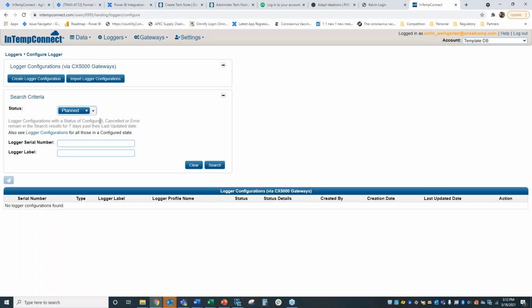How do we turn off the alarm after it's triggered? If you're using your gateway and have it set to download and restart, it will do that for you automatically. However, if you do a download and restart—either through the gateway or the app—and conditions are still bad, meaning the temperature is still too high or too low, it will alarm again immediately after. But if you clear that data and restart the logger, it will clear the alarm and you won't get notifications anymore.